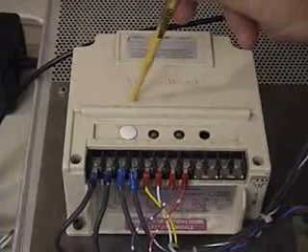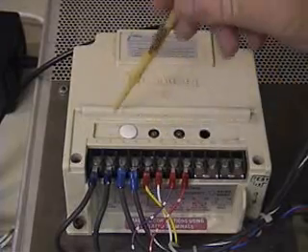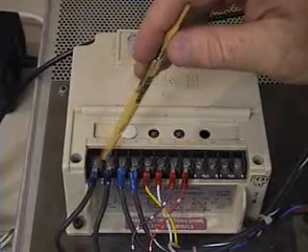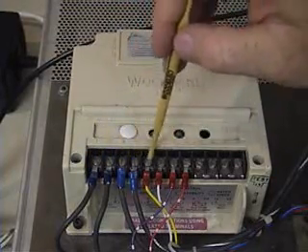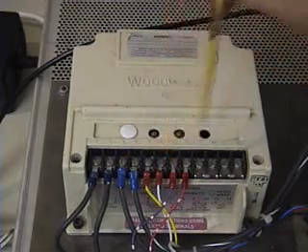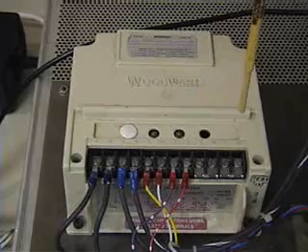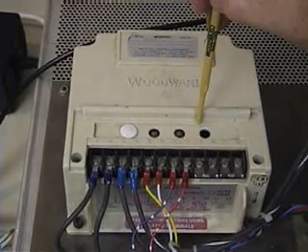This is the electric power governor. It actually controls the speed, sending its output to the actuator. The inputs to the EPG are 24-volt power, output to the actuator, input from the magnetic speed pickup. We have 3 potentiometers on top here to control the PID and adjust the PID parameters to the controller.